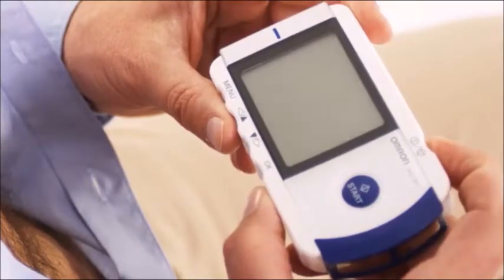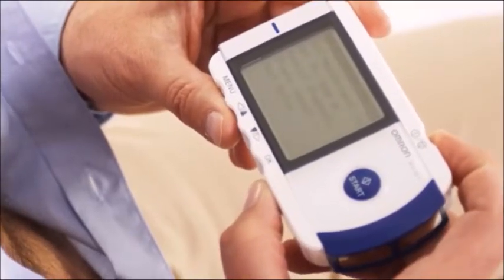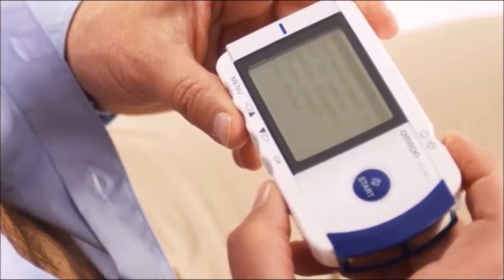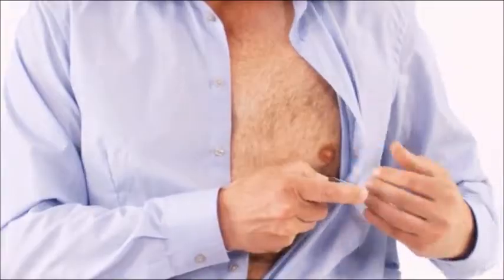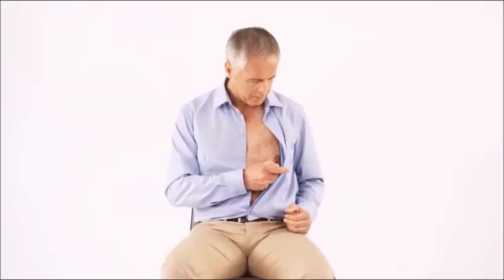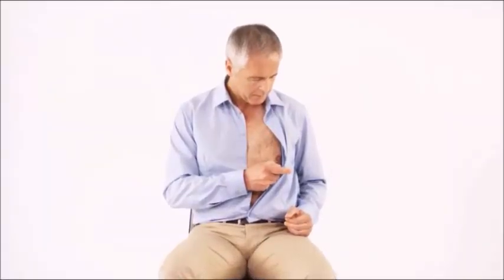See for yourself. Using the HeartScan is child's play and discreet as well. Ask your patient to sit down and bare the chest below the heart. Press the ON-OFF button to turn the monitor on. Place a finger closely to the two-finger electrodes on the right side of the monitor. Place the chest electrode directly onto bare skin.